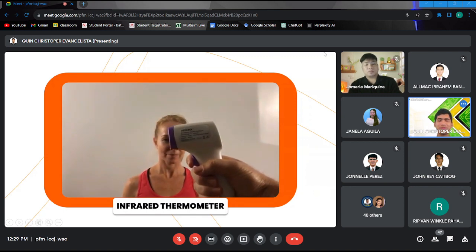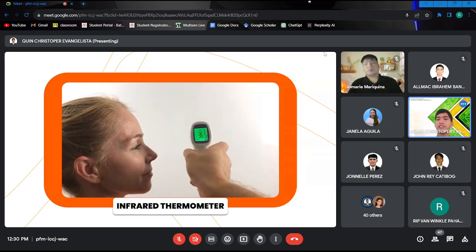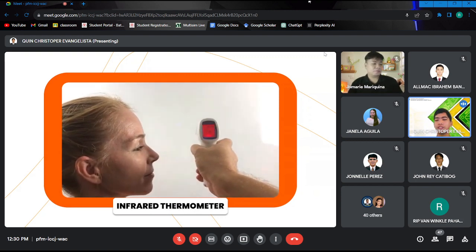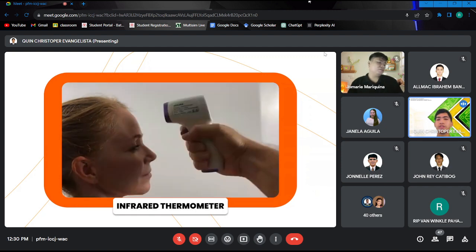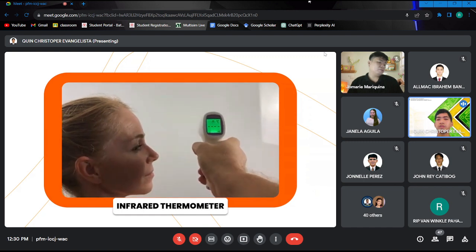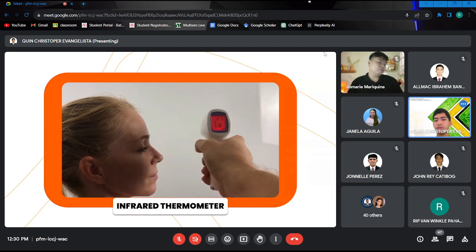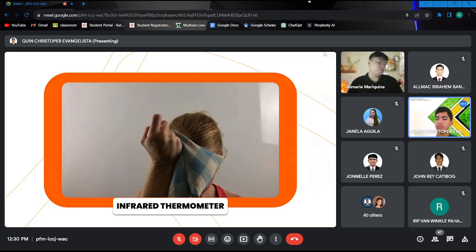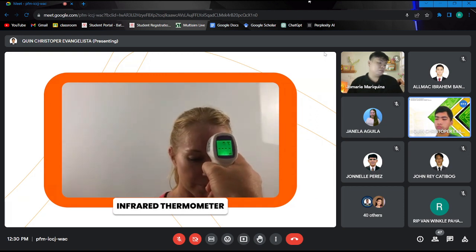Activate the device by depressing the trigger for 5 seconds. When taking a temperature sample, lightly depress the trigger, holding the gun in a stable position 3 to 5 centimeters away from the candidate's head. An accurate sample will give you a green reading. When the sample taken is incorrect, it'll indicate low. For demonstration purposes, we have the candidate hold a hot pack up against her head. When a sample is taken and the temperature indicates a fever over 38 degrees, the gun will flash red.